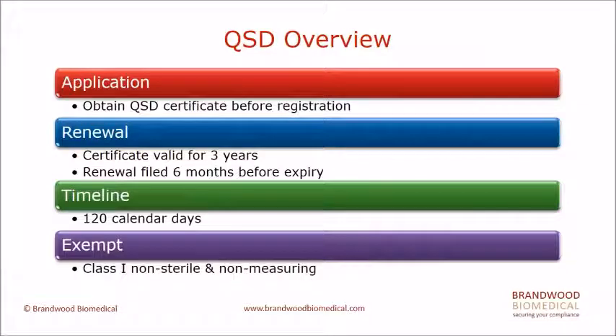Let's go through an overview of QSD. So the manufacturer needs to obtain the QSD certificates before product registrations. And the certificate is valid for 3 years. The renewal submission needs to file to TFDA 6 months before the expiry date. Either the new QSD applications or the renewal QSD applications, the reviewing timeline is 120 calendar days. It's a TFDA indicative timeline. For Class 1 non-sterile, non-measured devices are not required to have QSD certificate.